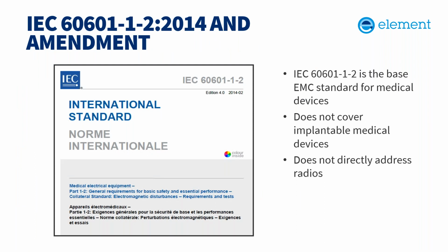So while 60601-1-2 is focused on EMC, it really is a safety standard. The testing inside, the requirements, what level you're supposed to meet, are for EMC. But the title of the standard, the focus of the standard, is basic safety and essential performance. Really, the users of the standard need to maintain basic safety and essential performance for their medical devices. The previous editions of 60601 were EMC standards. They focused on EMC, whereas this most recent edition, edition 4, and then with Amendment 1, so edition 4.1, is a safety standard. Radios are mentioned as potential RF threats, and there is a clause on addressing emissions from radios in the medical device, but it does not directly address radios in the standard.